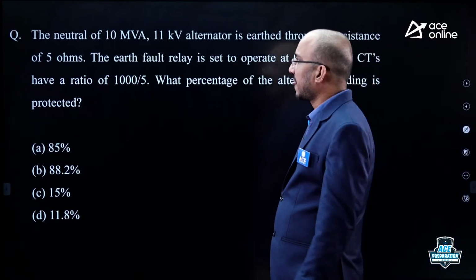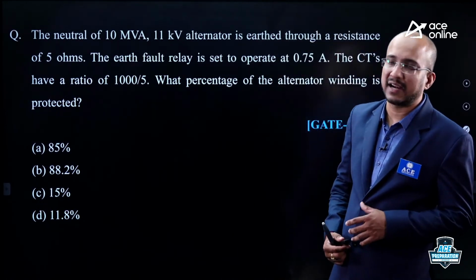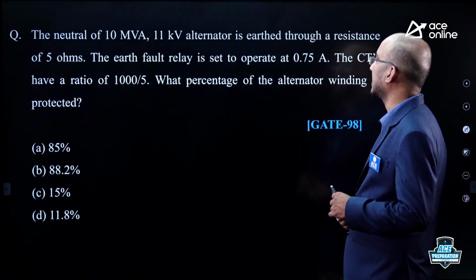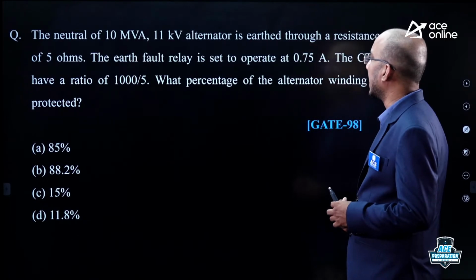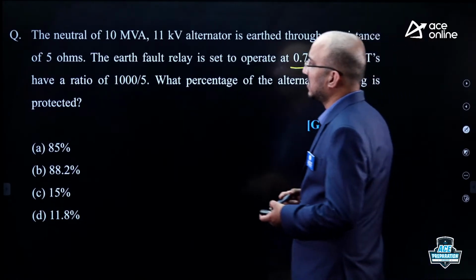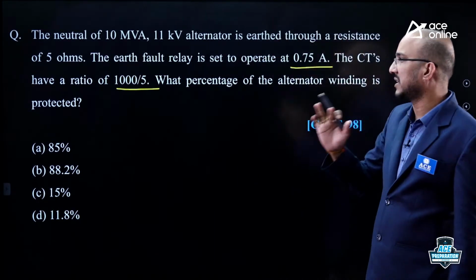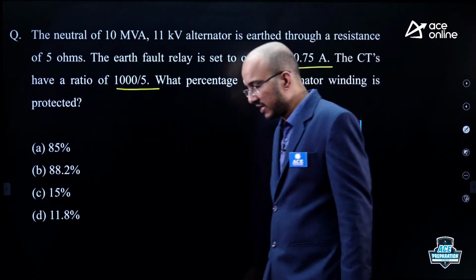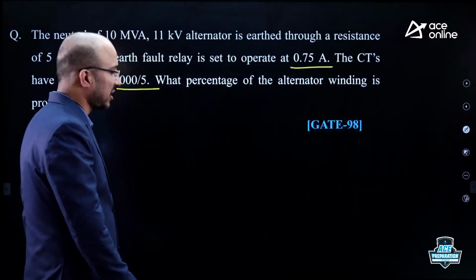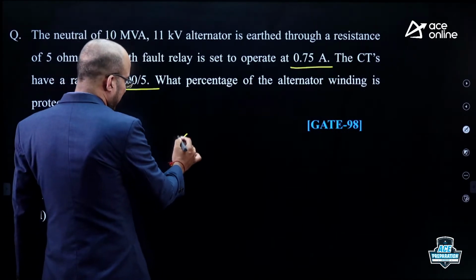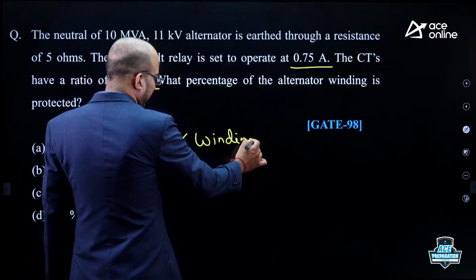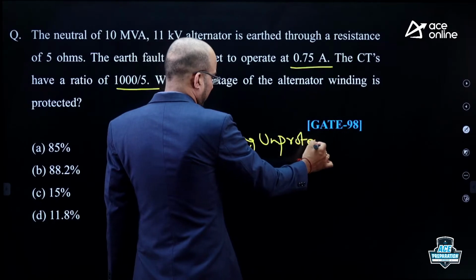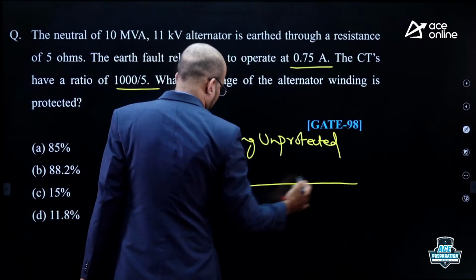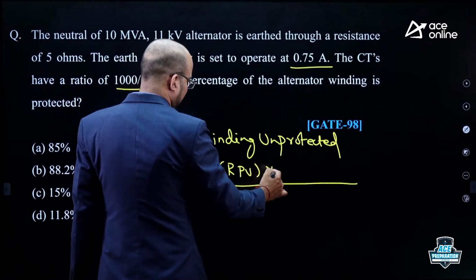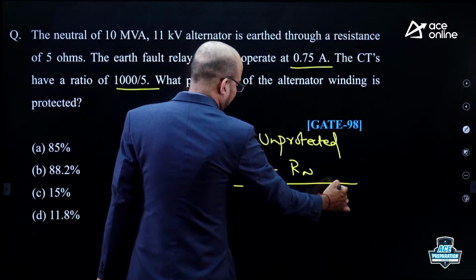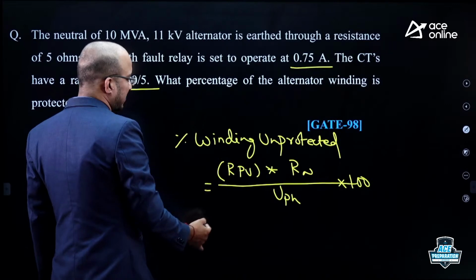Now, let us observe here. This is a question that was asked based on the protection of alternator. The neutral of a 10 MVA 11 kV alternator is earthed through a resistance of 5 ohms. Earth fault relay is set to operate at 0.75 ampere. CT ratio is 1000/5. How much percentage of winding is protected? Generally, due to resistance grounding of neutral, a certain portion of the stator winding is left unprotected. So, first let us get the percentage winding unprotected. The percentage winding unprotected is equal to relay pickup value multiplied by neutral resistance grounded, divided by phase voltage, into 100. The relay pickup value is to be transferred to the primary side.